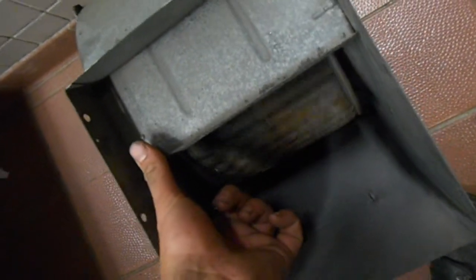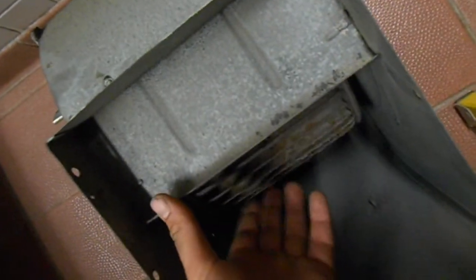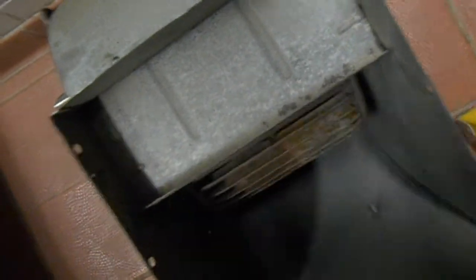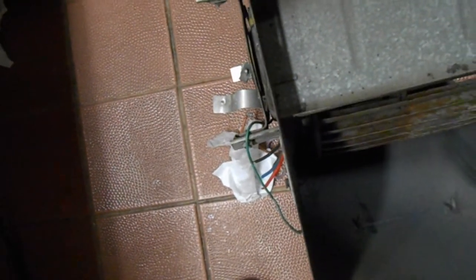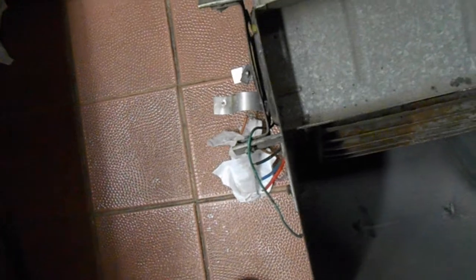That was causing it to draw more amps than normal and blow the capacitor. So, rather than mess with this, we're just going to replace this fan motor so I don't have to get back up here again. This is really hard to get to. You have to take the supply deck down and everything. It's a real mess to get up there. So, we're going to replace it with a new capacitor, a new motor.